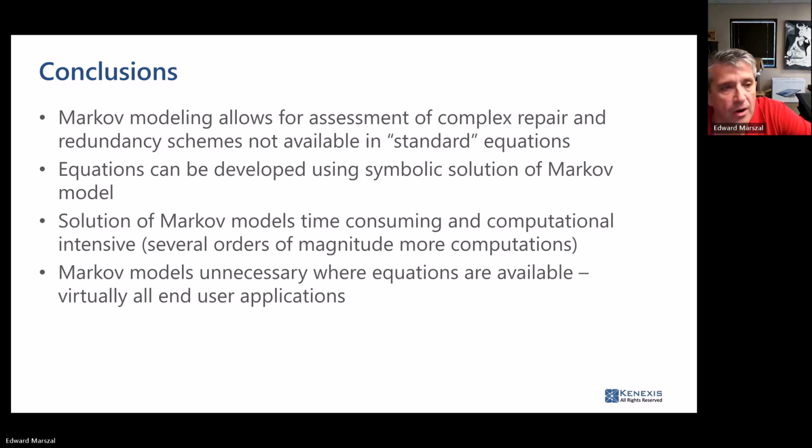Okay, thank you. All right, so wrapping up a little bit in terms of conclusion. Markov models are valuable. They are going to allow you the assessment of complex repair, complex redundancy schemes, different handling of multiple different failure modes that aren't available in the standard equations.